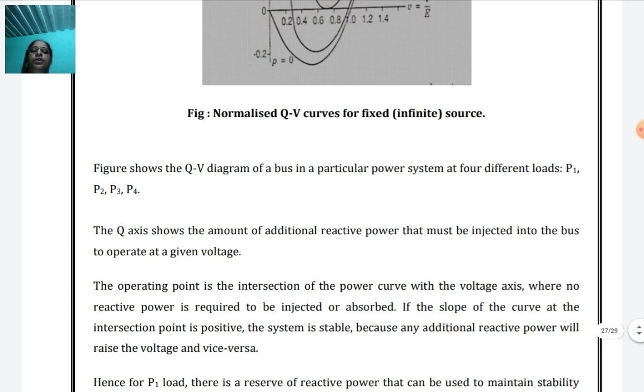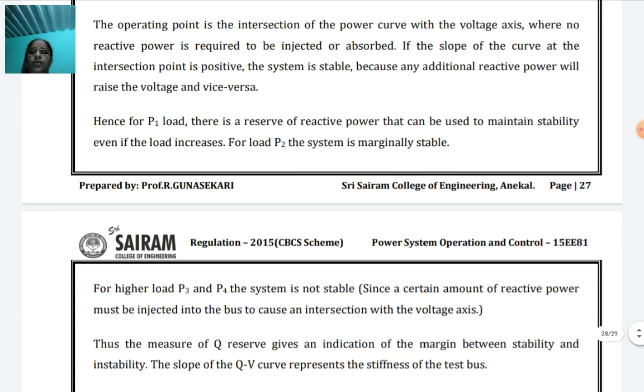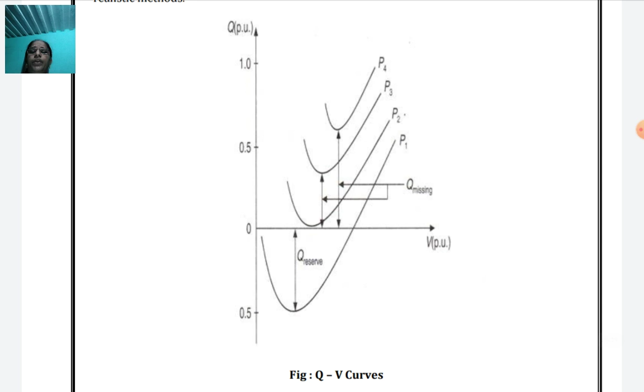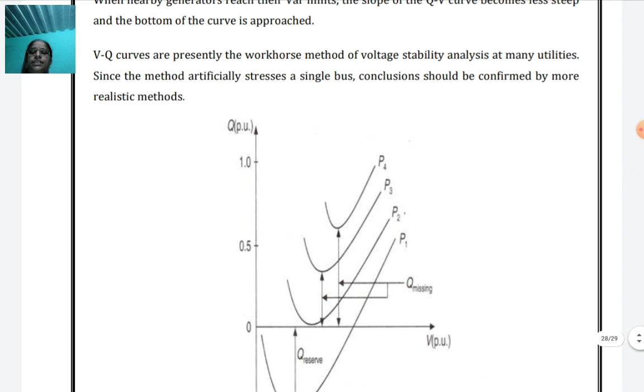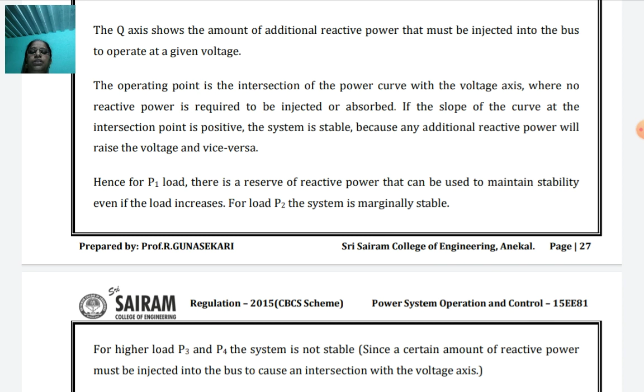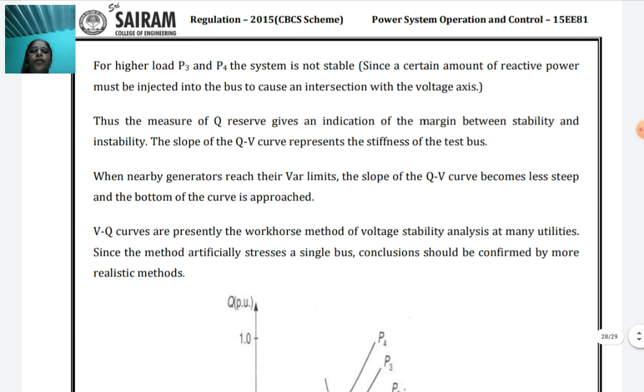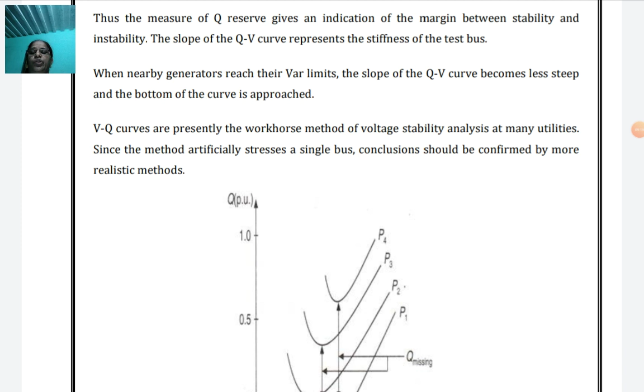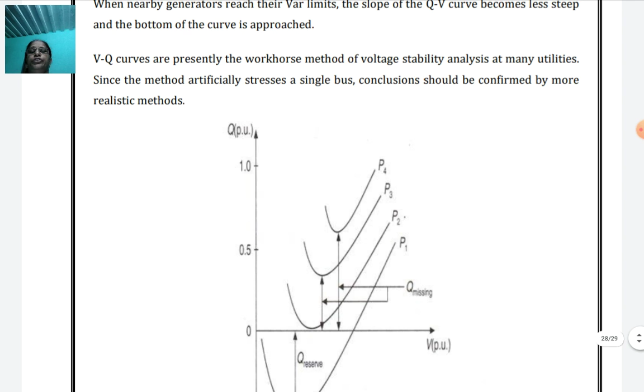So we have different loads, P1, P2, P3, P4, that means 0, 0.25, 0.5, 0.75 and 1. Now here you see the PV curve, P1, P2, P3, and these are the 4 in the QV curve. In the QV curve, for the first load P1, there is a reserve of reactive power that can be used to maintain stability even if the load increases. But for the load P2, the system is marginally stable. But for higher loads P3 and P4, the system is not stable. Therefore, the slope of the QV curve represents the stiffness of the test bus. The QV curve becomes less steep as the bottom of the curve is approached.